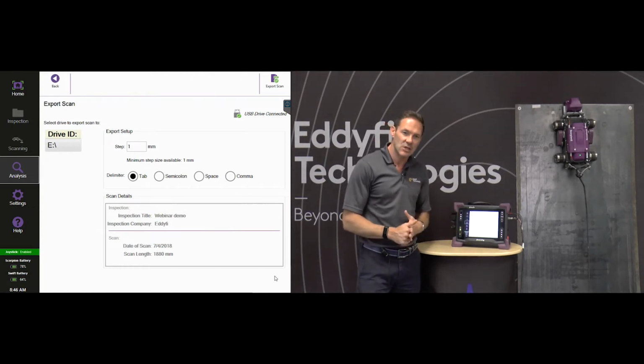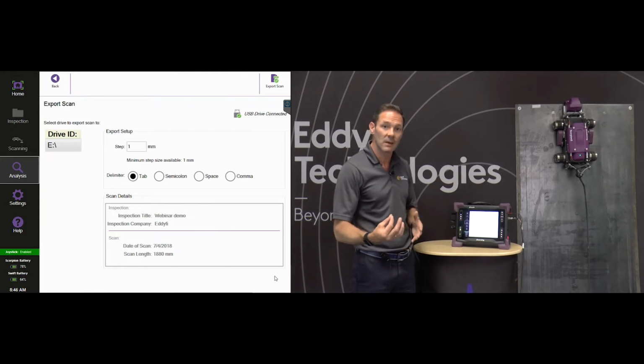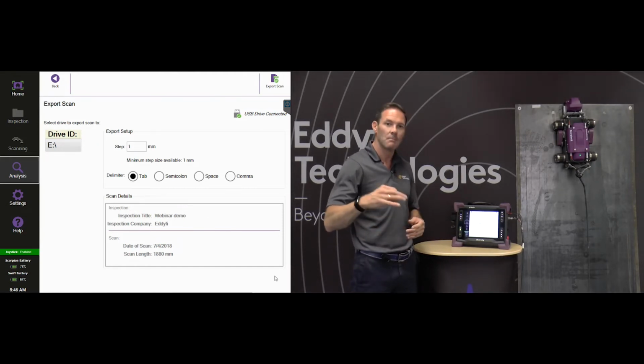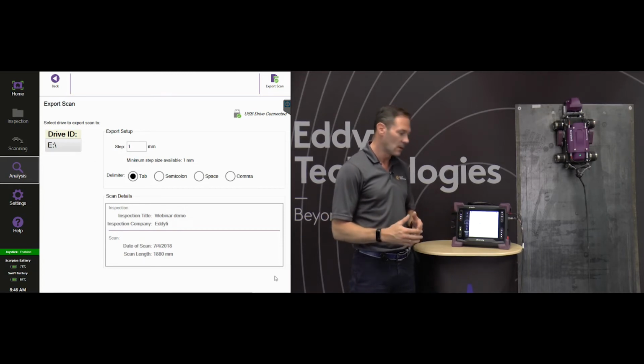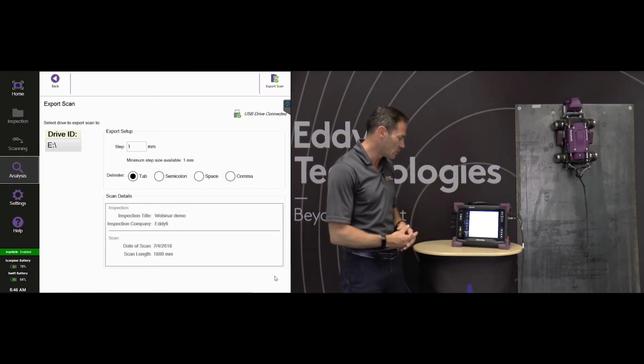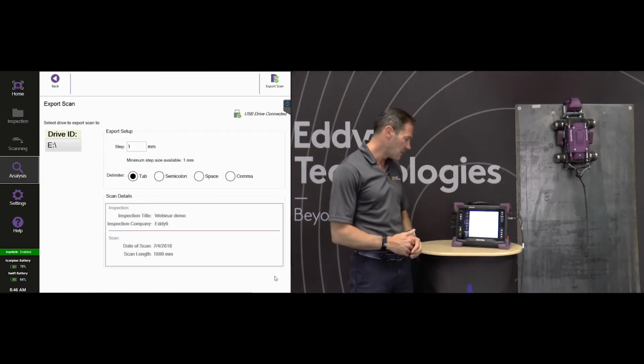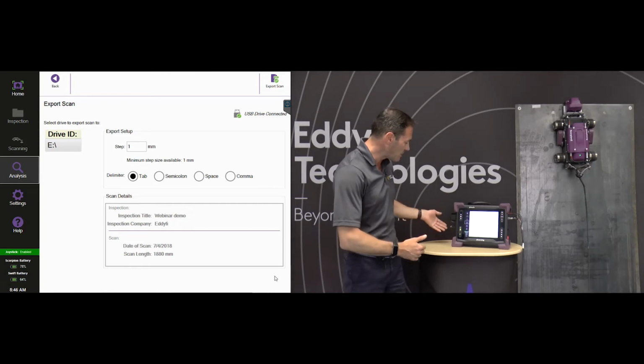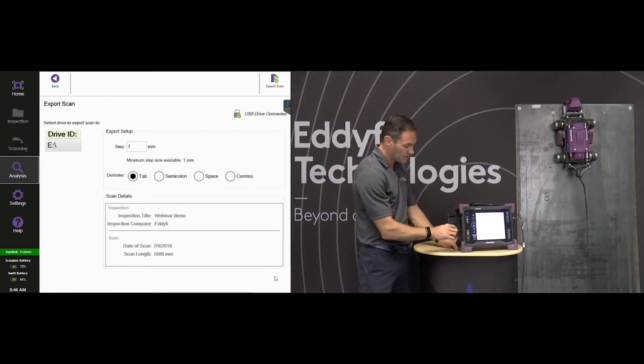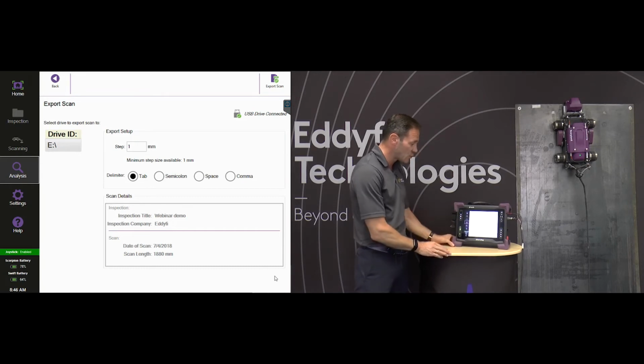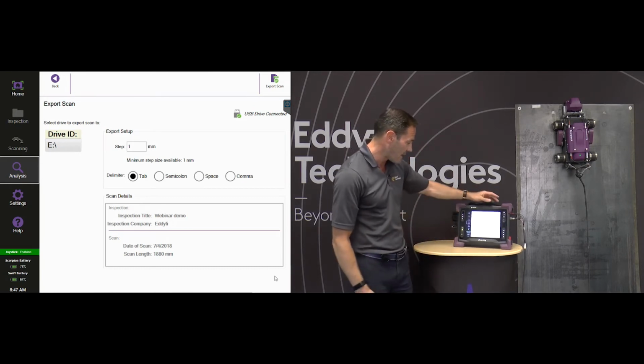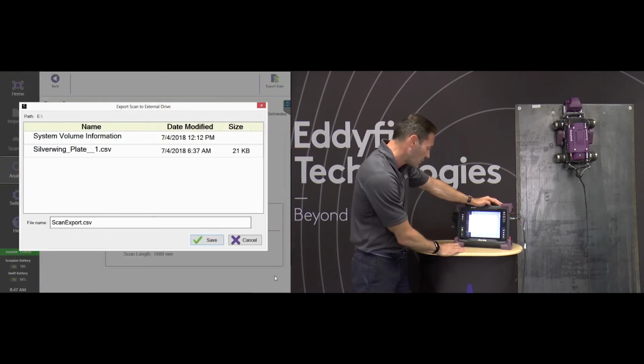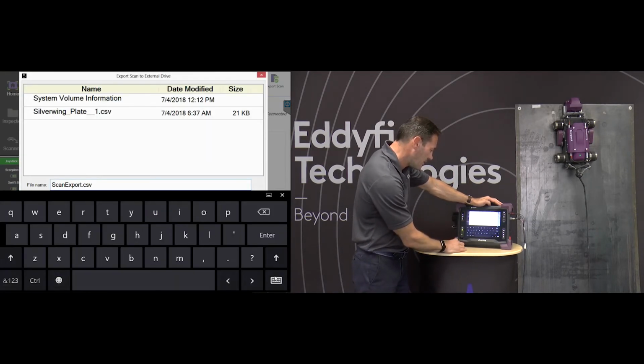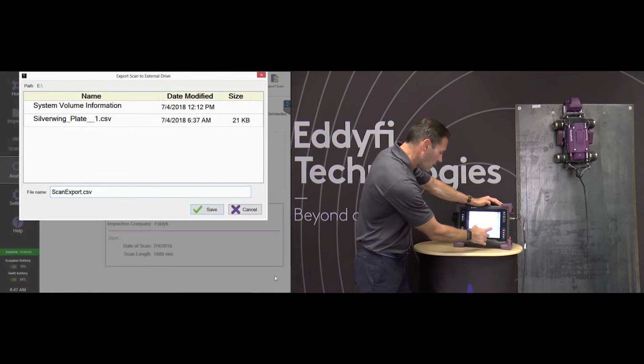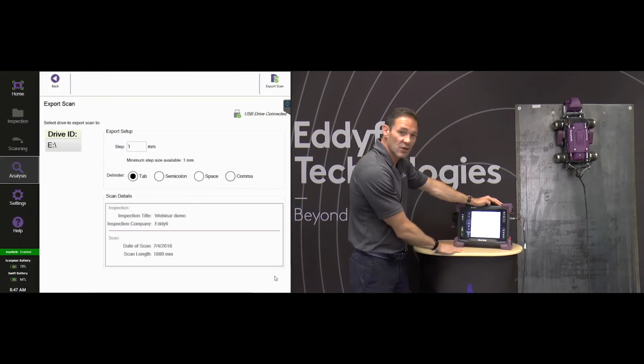I can add a step, so the system makes a measurement every millimeter, but I can choose to output a measurement every 10 millimeters instead, so you'll have less data on your scan length. I can choose my delimiter if I need to, and then add a USB key. The USB key is recognized as drive E in the file, and all I have to do is save the export, give it a name, and save the file. Now the CSV data has been saved to file.